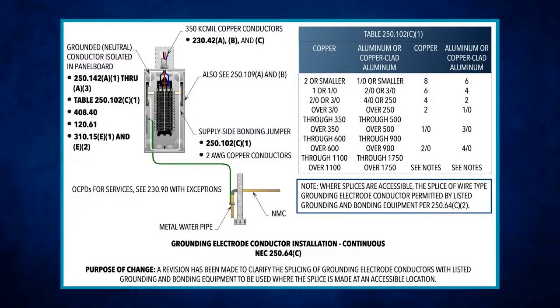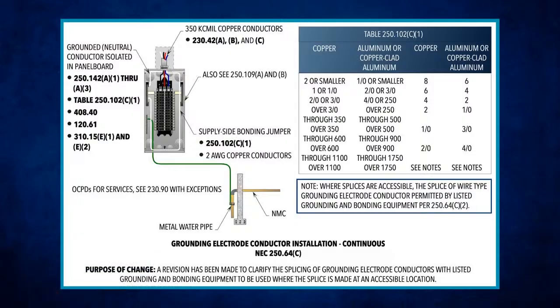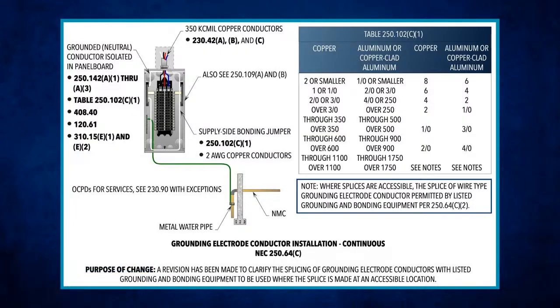See, that is my whole point behind this. It doesn't matter what size service we have, man. Matter of fact, show me where it matters on the size service. Give me that section. The concrete encased electrode is tied into the building steel. You're combining electrodes. Tell me where the size service matters. The only way he can get to the size service is he has to look at Table 250.66. Okay. So let's see what 250.66 says.